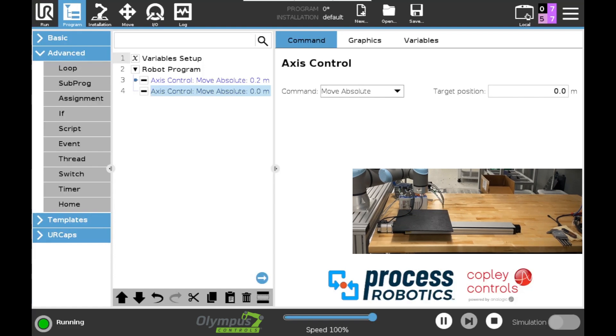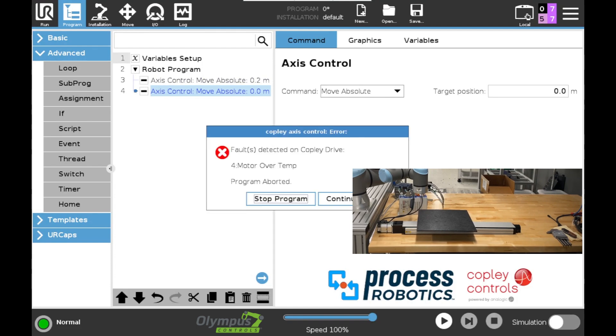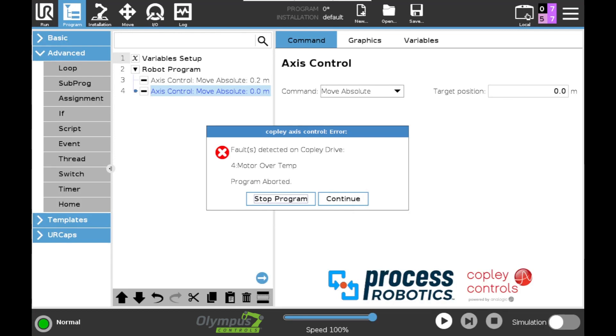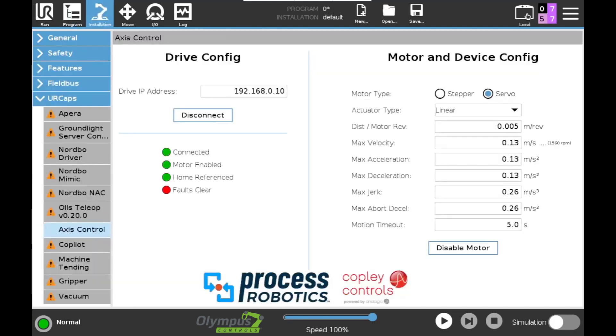Now say for instance, a fault is going to occur. I can trigger that manually in my configuration right here and see what happens. So the drive becomes disabled and it throws a popup onto the teach pendant. You can see I manually triggered this motor over temp with one of the IO's I have available on the Copley and this terminated the program. I'm going to go ahead and hit continue and our program has ended. When I go back into the installation tab I can see that we have a fault.